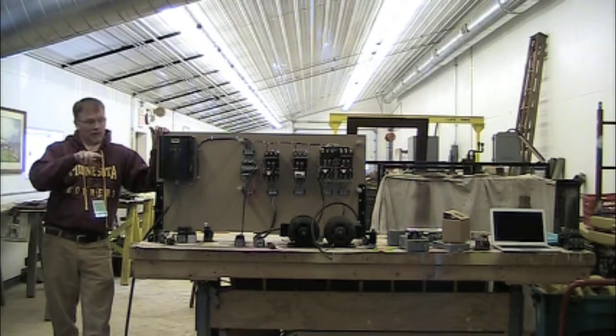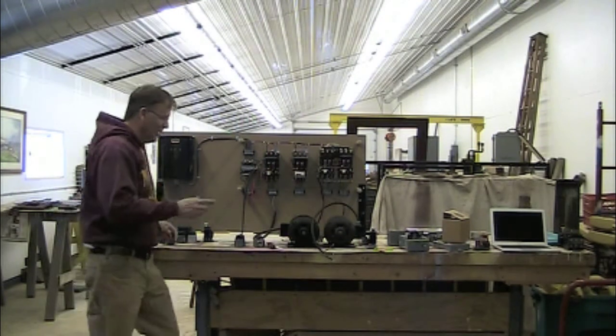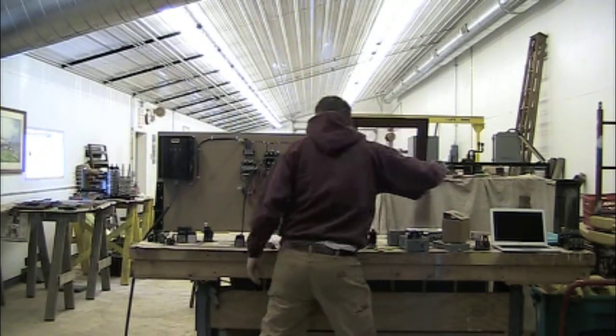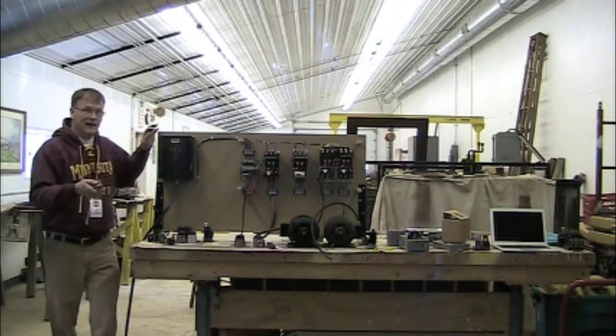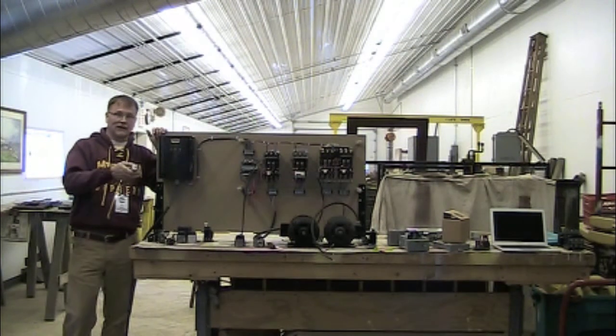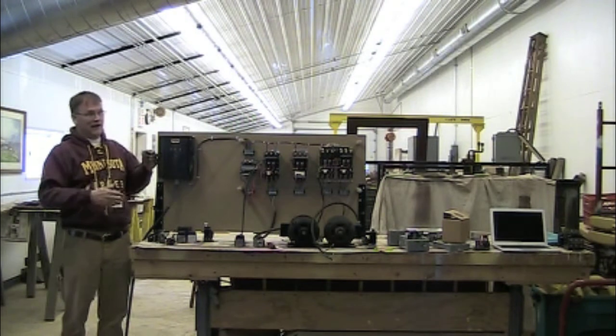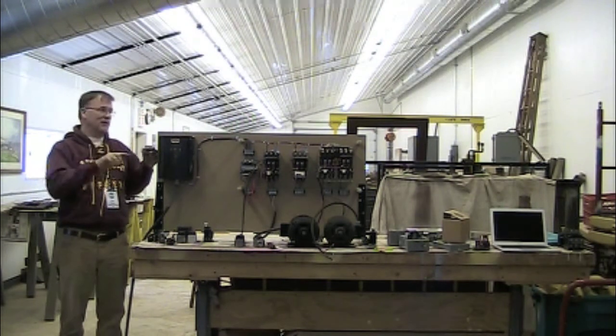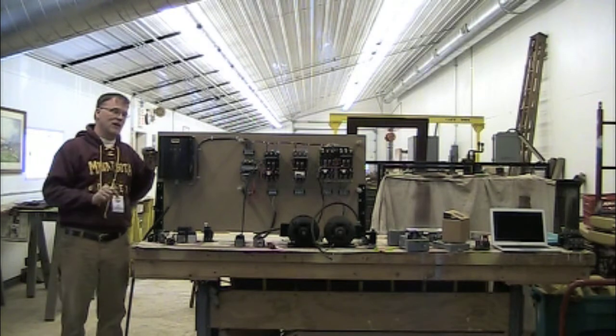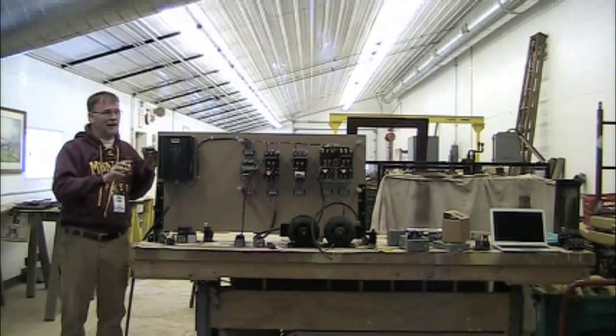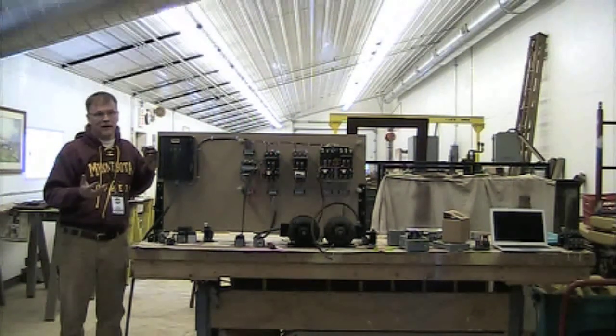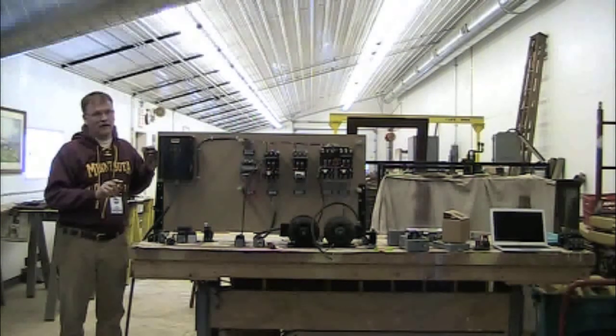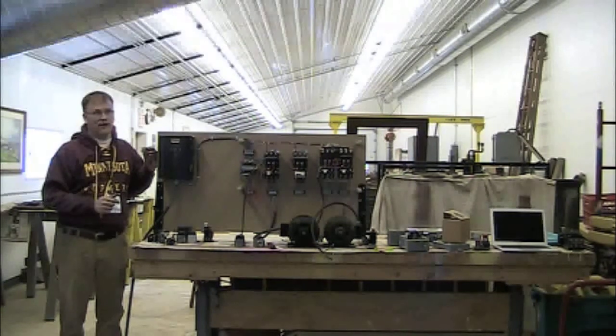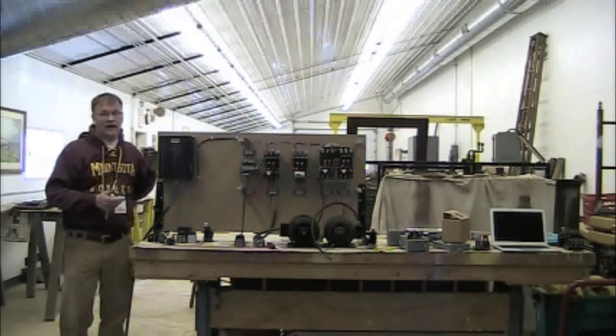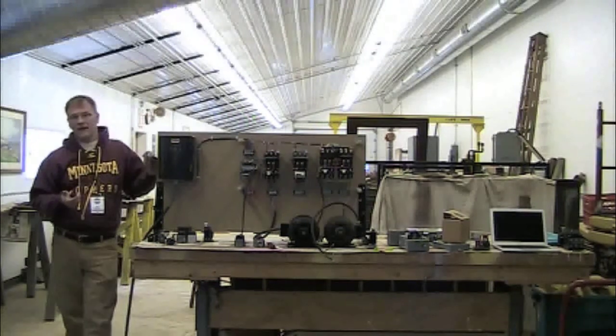You can have a separate little industrial control relay. You can just set up a secondary little control circuit so that, like on your air compressor, if you want it to run automatically, you press the start button, it energizes the circuit, and it holds as long as there's power there, so the thing can cycle on and off. But if you lose power, the thing's off and it's not going to start again until you go press that reset button and bring it back up. And that's actually a good way to control things.